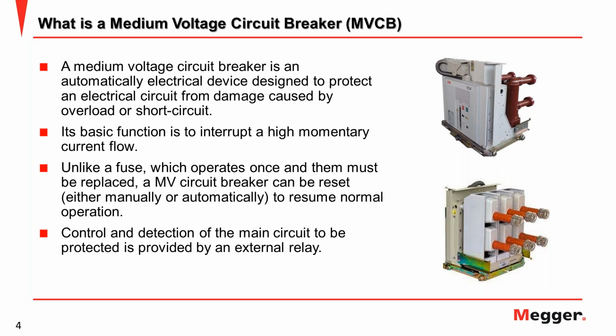So in other words, a CB or circuit breaker is an electrical switch designed to protect the system from damage conditions caused by excess current, like overload or short circuit. This is the definition of the MV circuit breaker. The basic function of the breaker is to interrupt current flow after a fault is detected by another component, in this case the relay, and then the breaker can take action to interrupt the fault.